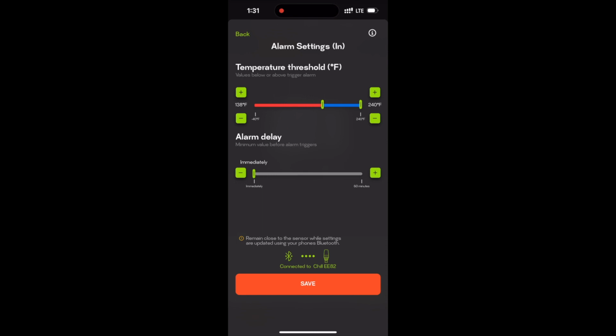Next, we'll adjust the upper and lower level thresholds for when alarms will trigger. We can choose to have alarms trigger immediately or adjust the timing so that they're delayed before they send an alarm. This helps avoid nuisance alarms.